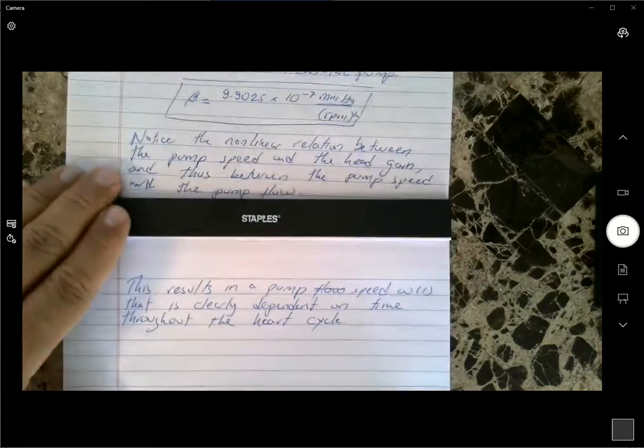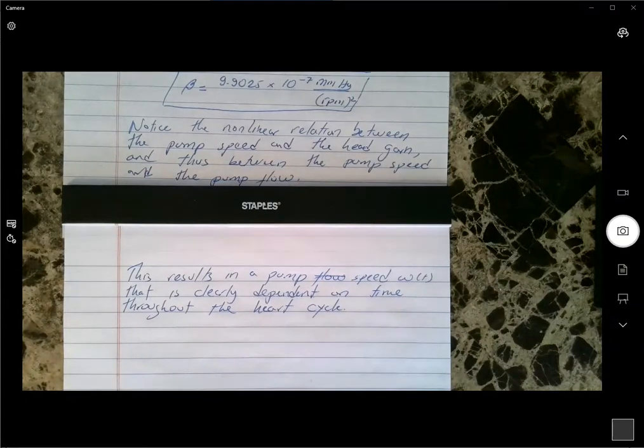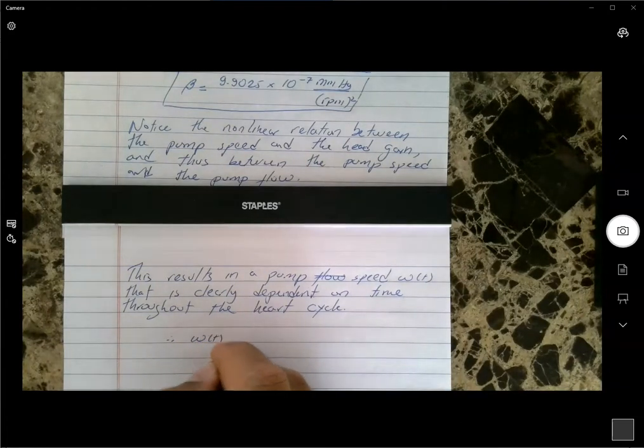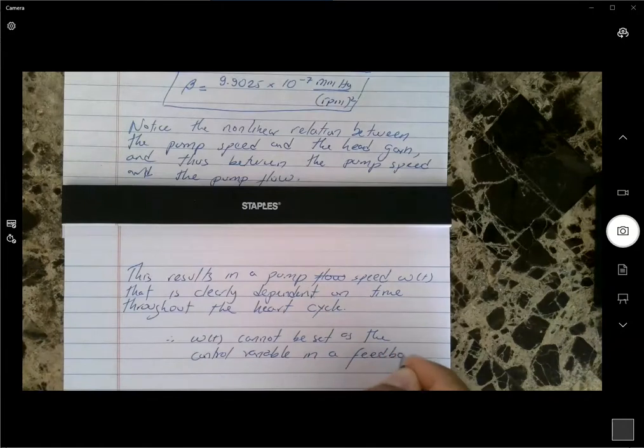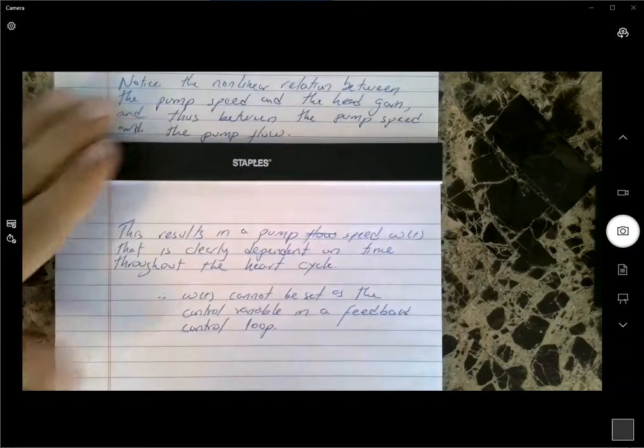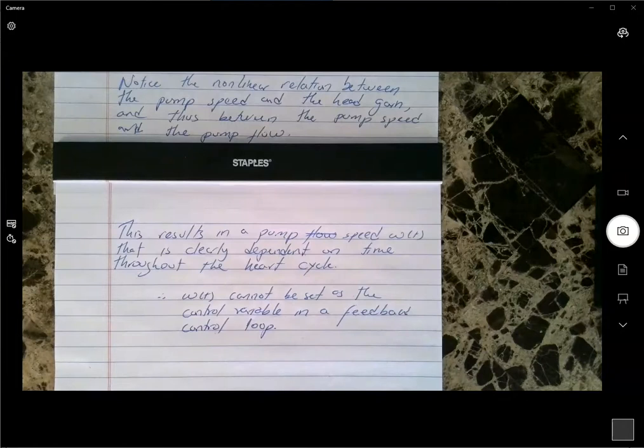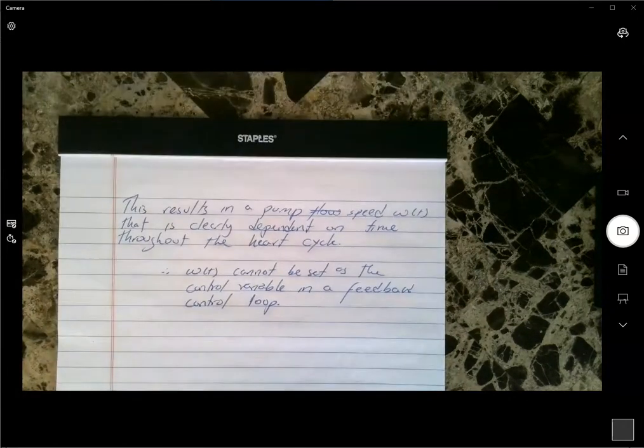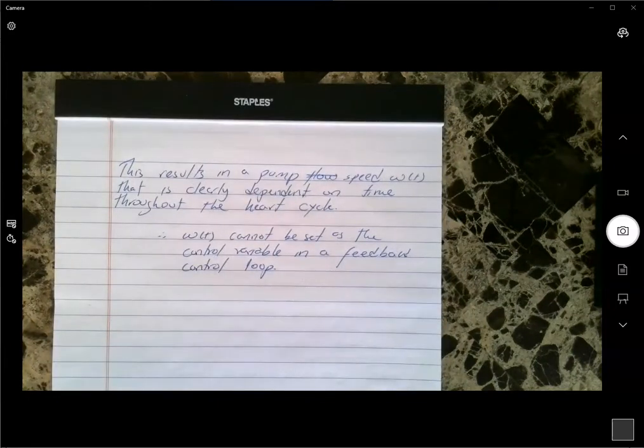So we might see a signal of the pump speed that goes up and down with the heart cycle. So this omega of t, which is the RPM, cannot be set as the control variable in a feedback control loop. This is a variable that is really accessible, a number we can measure very easily through optical sensors. We have a shaft that is rotating at a certain speed, and we can just calculate it directly. However, it is not going to be possible to use it directly.